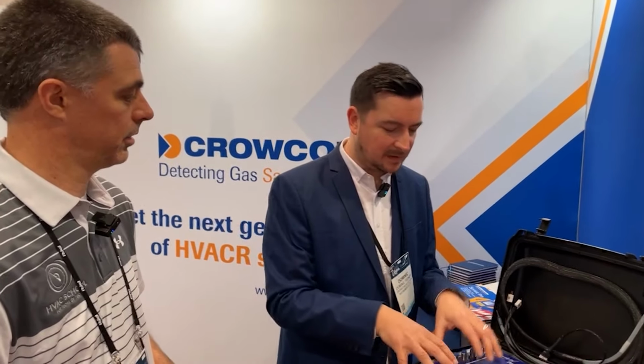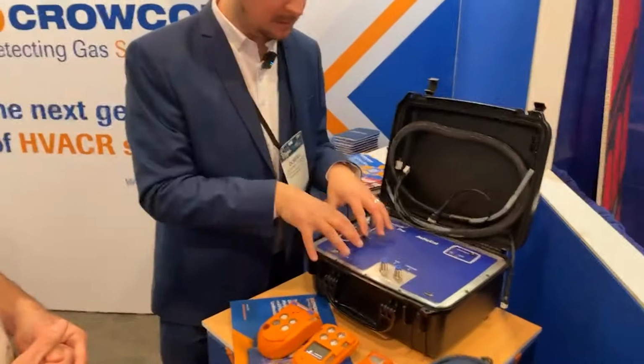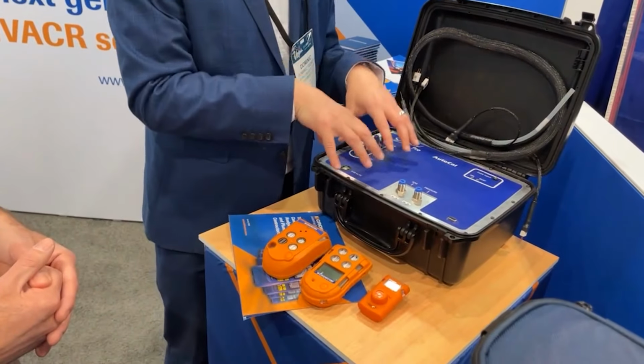So we've made the process easy, and what we're doing is allowing these automatic calibration jigs to be installed with our partners and suppliers. We've got them at our Kentucky HQ, but we've also got them out in the field, local to engineers. So rather than sending it back, if your distributor has one at their location, you can walk in, plug it in, and twenty minutes later you're out the door with a new certificate in hand.